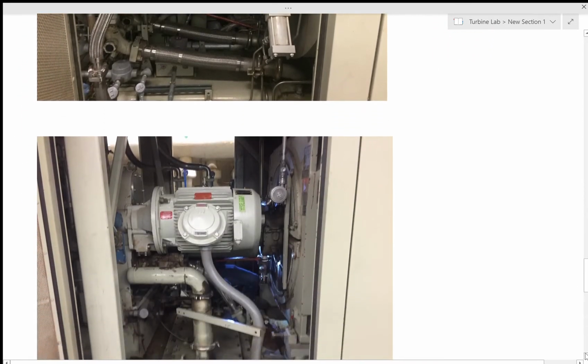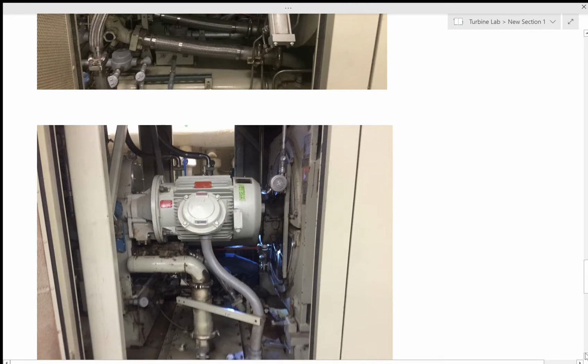And then I was telling you about the motor that turns the turbine and gets it close to synchronous speed. This is a three-phase motor, runs about 1725 RPM. They start injecting current onto the rotating mass of the generator, the rotor, the windings of the rotor, and once they get everything going, then all they have to do is put that current on there, and it sets up that magnetic field, and the turbine picks up that last 75 RPM and turns at synchronous speed, which in this case, again, is 1800 RPM.